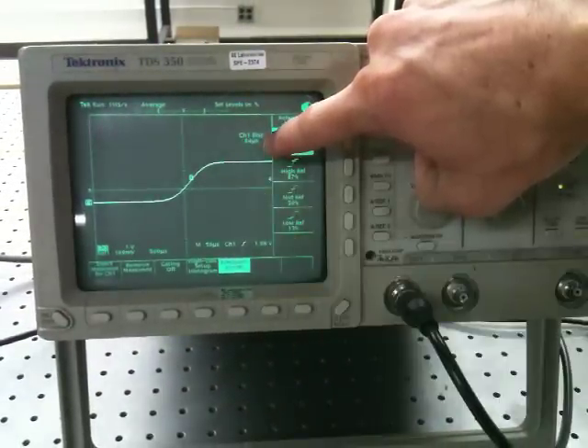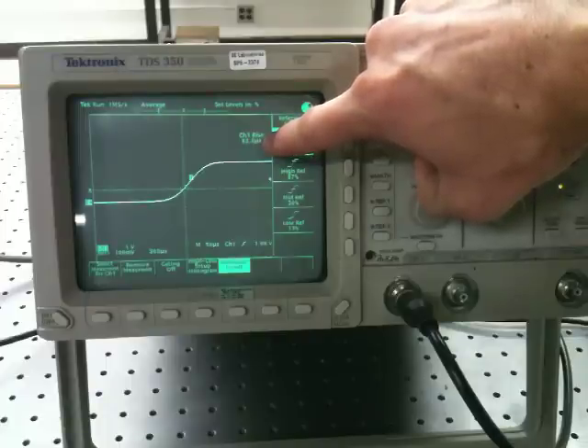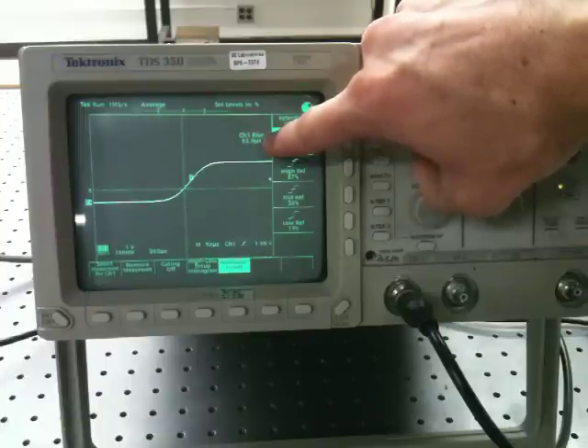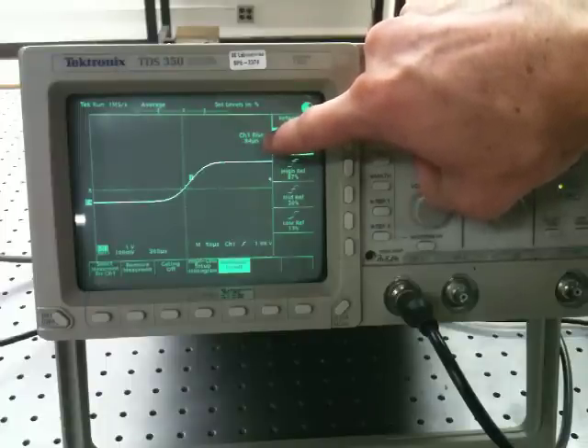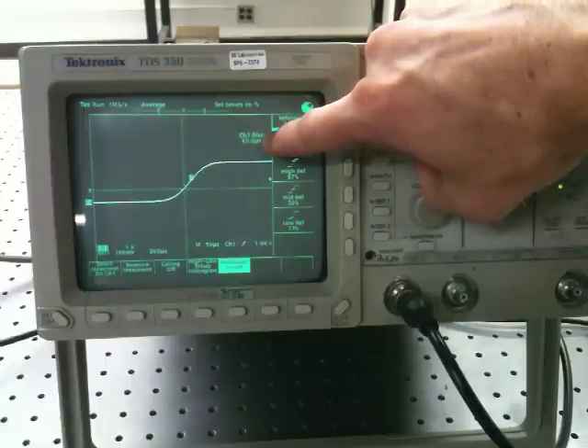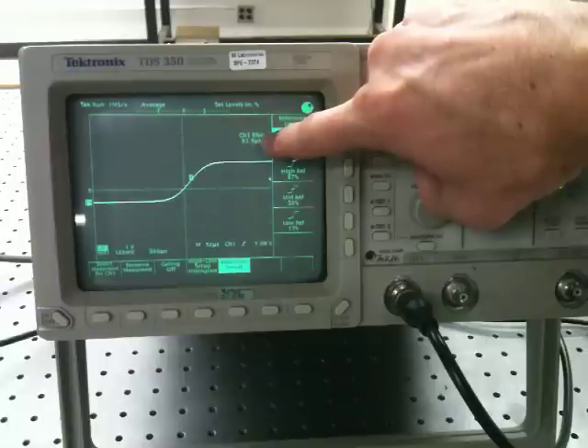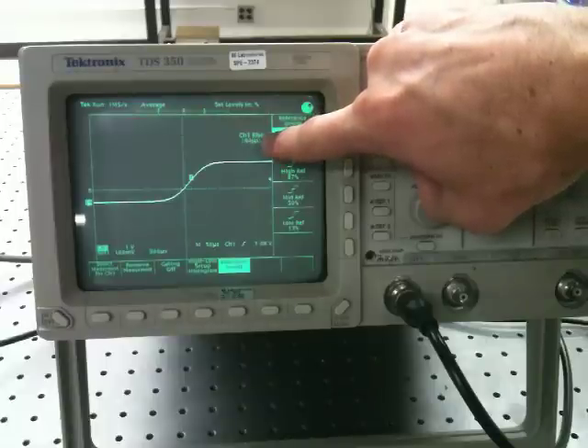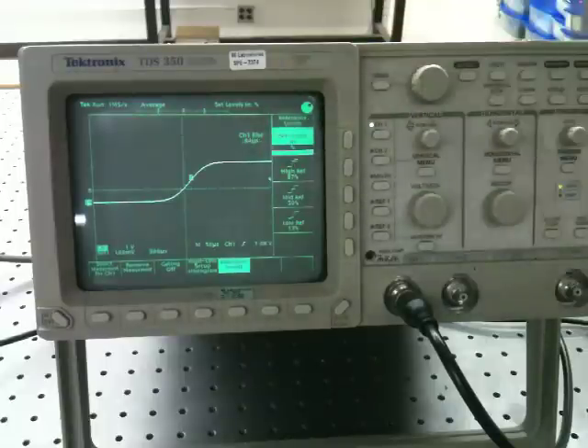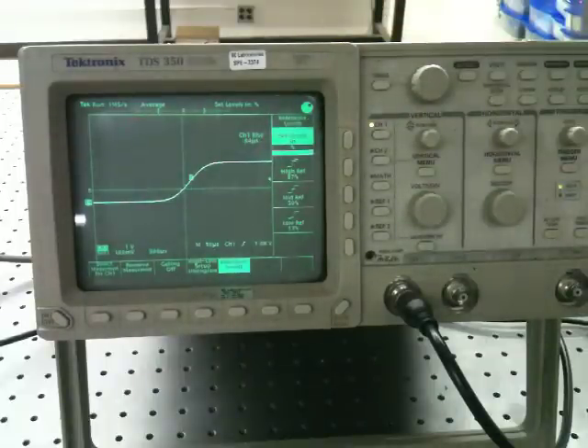I can then record that measurement value, multiply it by the velocity of the chopper wheel at the point where it's passing through the beam, and I will have a measurement of the Gaussian beam radius at the location of the chopper wheel.